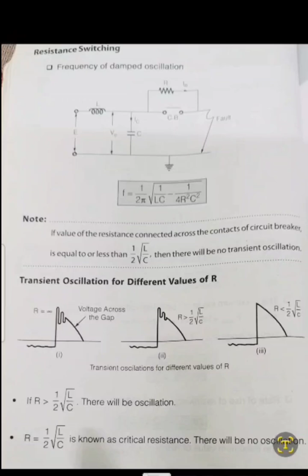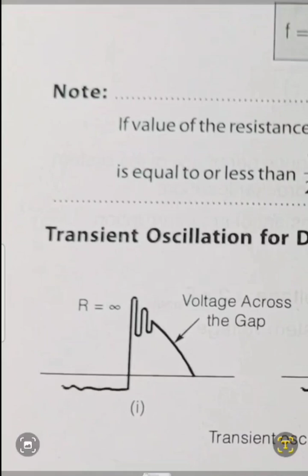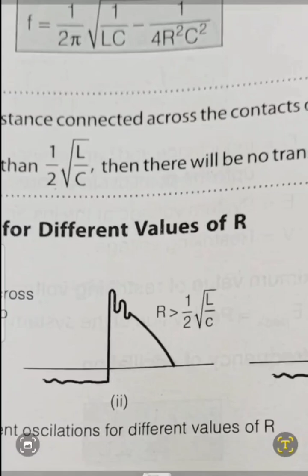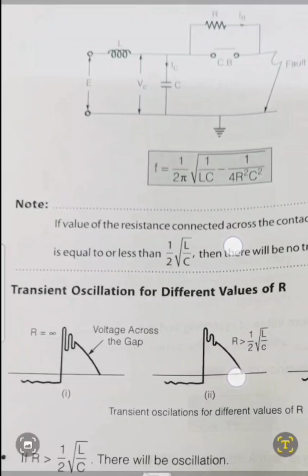Now consider transient oscillation for different values of R. First, if R equals infinity, consider the voltage across the gap. Second, if R is greater than 1 by 2 root over L by C, there will be oscillation. If R equals 1 by 2 root over L by C, it is known as critical resistance, and there will be no oscillation. So we have to maintain at most 1 by 2 root over L by C as the resistance value. Above that, the system will oscillate, which is not suitable and very dangerous.